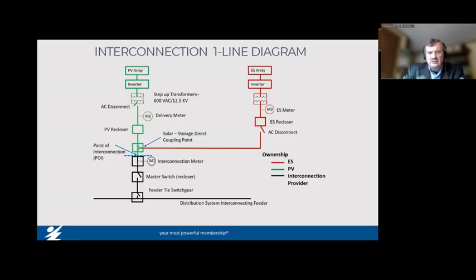Therefore, when we're charging, all the solar generation goes into the batteries. None goes to the grid, and there's no grid energy coming into the batteries either. That interconnection meter basically reads zero when we're charging the batteries. Once the batteries are all charged up, the controls say okay, we're done charging, and then the solar proceeds to go back out onto the grid.